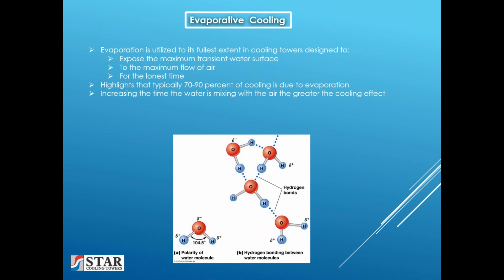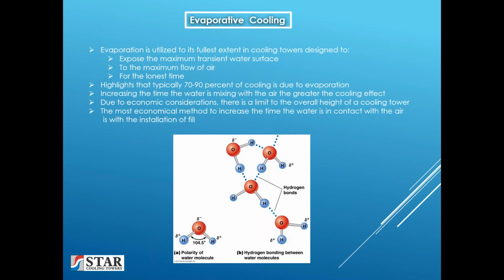Obviously, by increasing the time the water is mixing with the air, the greater the cooling effect. But due to economic considerations, there is a limit to the overall height of a cooling tower. So the most economic method to increase the time the water is in contact with the air is with the installation of fill.